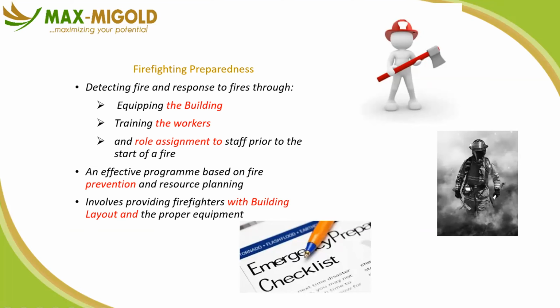Then we have what we call firefighting. And it's not the firefighting, it's where we have the emergency response. So I said for your strategy, there must be prevention, there must be protection, there must be suppression, and there must be firefighting. So use either the water truck, that's your fire truck, or fire extinguishers, or whatever falls under firefighting. And because it needs human intervention, that means you have to have a team that is well trained to respond to fire.